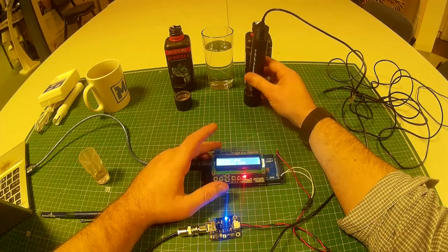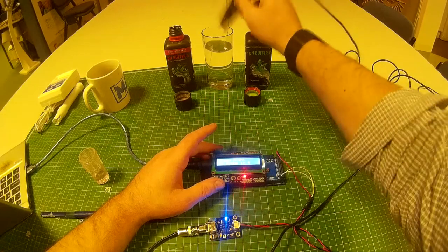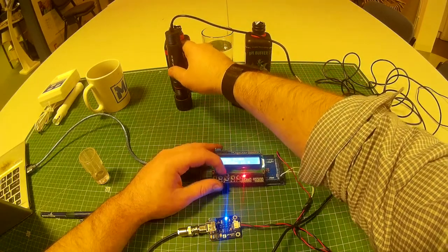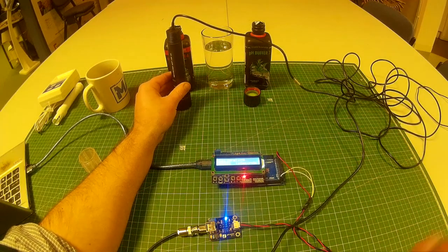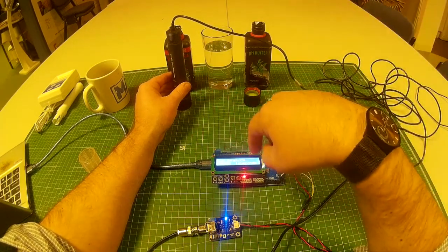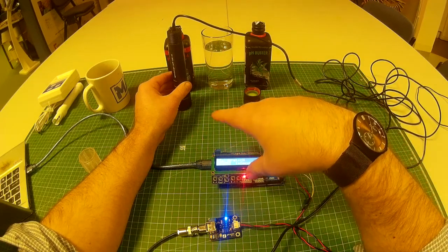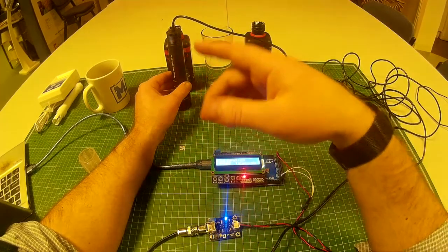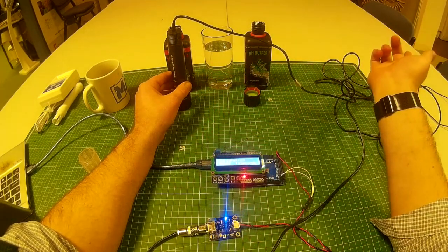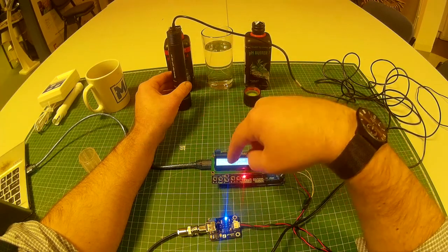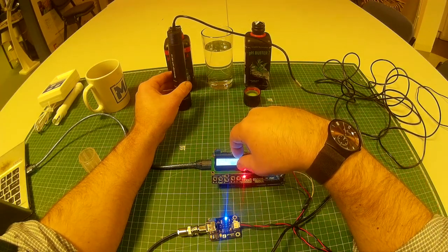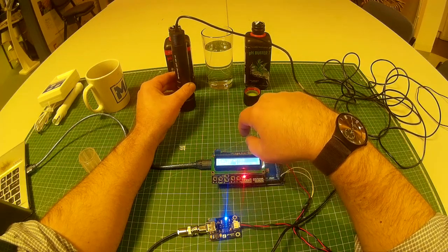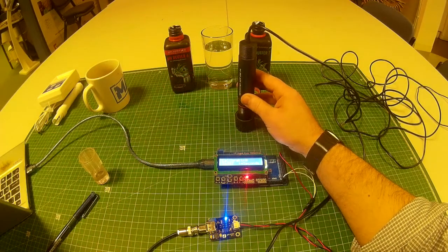Now it tells you to rinse and place it in pH 4. So that means rinse it in some distilled water. Place it in pH 4 and press right. Now what this does is it calibrates the pH 4 value as well. It takes two minutes. It'll also check the probe life. If you want to know a little bit more about how we check the probe life, check the blogs out. But for now all you need to know is every time you calibrate, the health screen's updated. So it'll tell you if your probe's in good health or bad health.